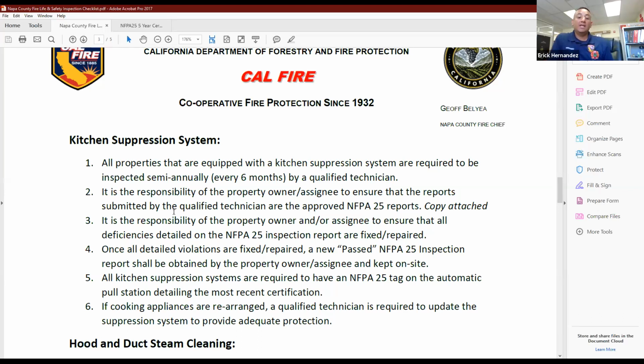In addition to that, now let's talk about the hood. The hood system is basically the exhaust system. So typically you would have a power wash company come out to the property, again, every 6 months, semi-annually. And they usually just get on the roof and start scraping and use solutions to properly clean any buildup in the plenum, and also they clean out all the filters.